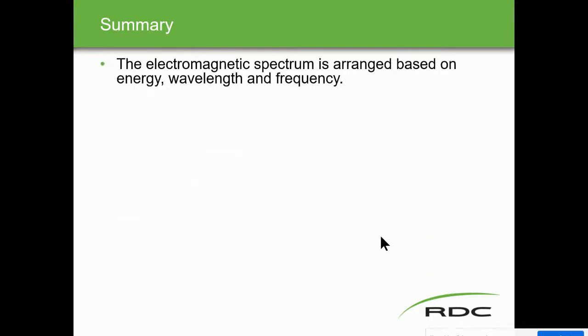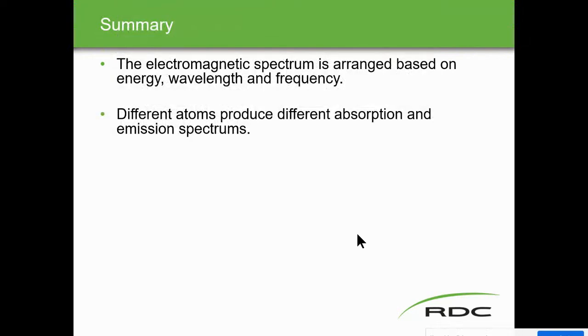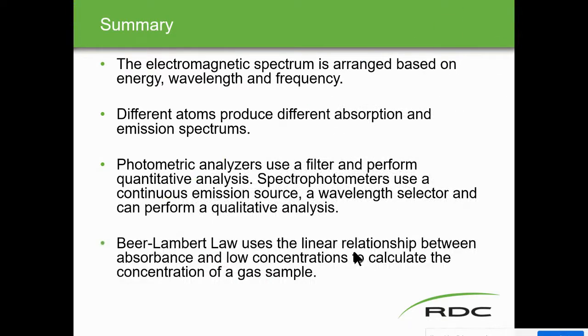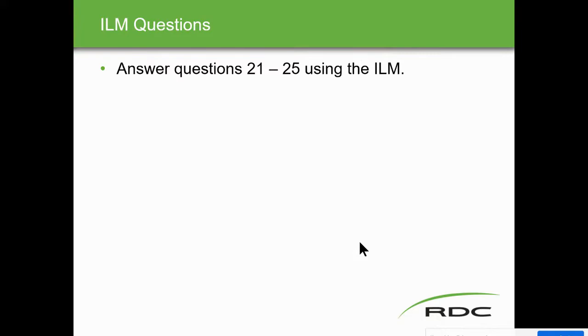Summary: the electromagnetic spectrum is arranged by energy, wavelength, and frequency — shorter wavelengths have more energy. Different atoms produce different absorption and emission spectrums. Photometric analyzers use filters for quantitative analysis; spectrophotometers use a continuous emission source with a wavelength selector. Beer-Lambert's law uses a linear relationship between absorbance and concentration at low concentrations, deviating near 100% concentration. That concludes the spectroscopic analyzers module.